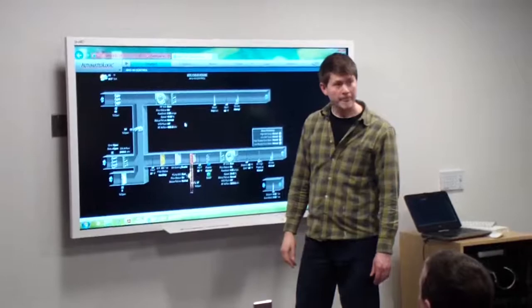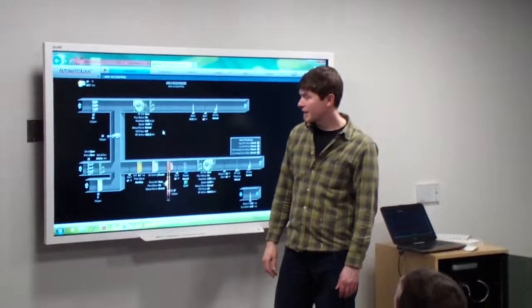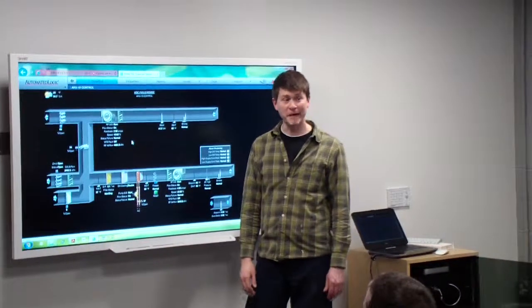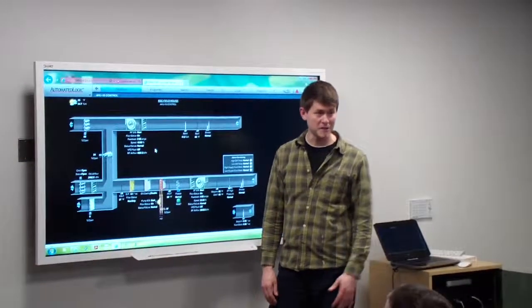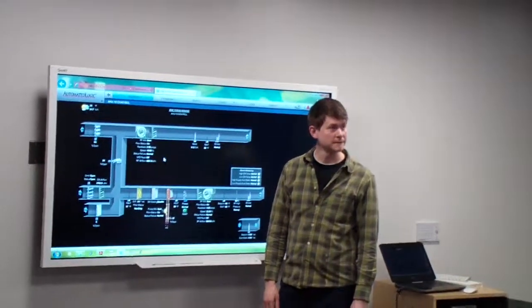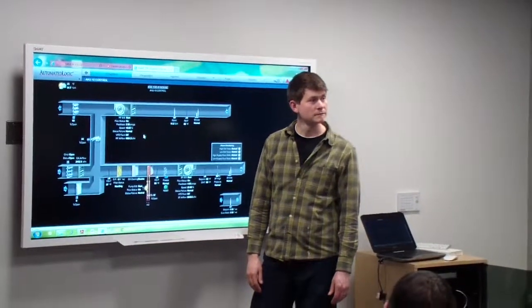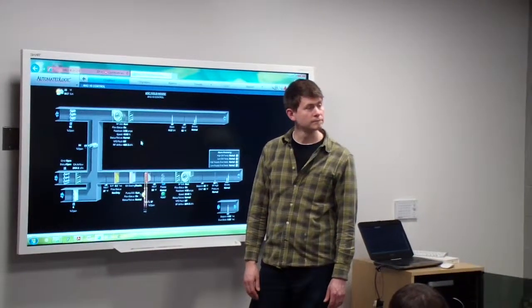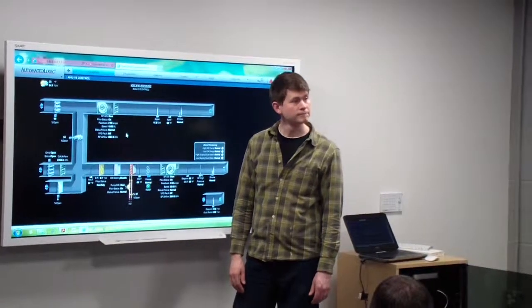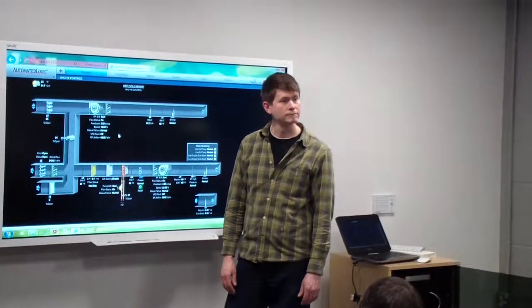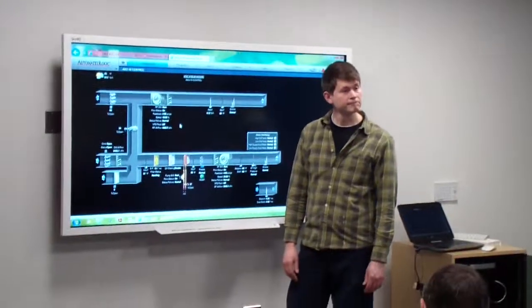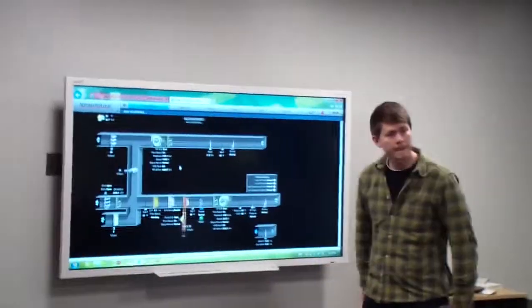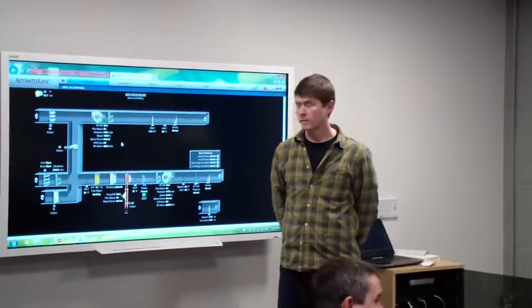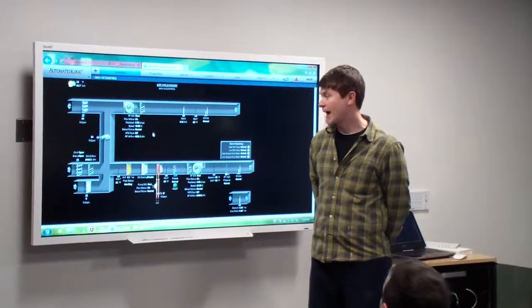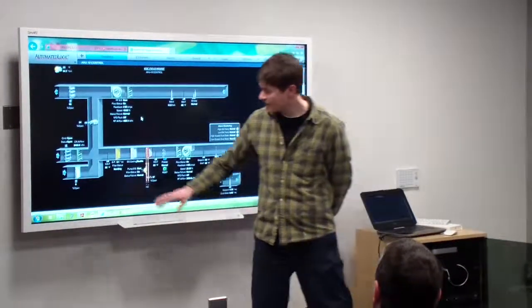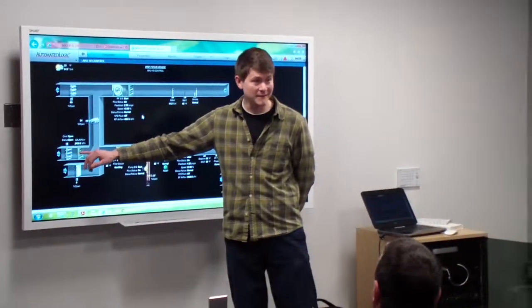Is that appropriate for a fitness space? I don't know the answer to that. That is what it called for in the spec, so that's appropriate to what the engineers believed. It should be based on usage, so we can question the engineer, but the design criteria would count that it is a fitness area, and so it should have the appropriate fresh air for that space. But is there ability to adjust that if we need to, or not? At this point, this is based off of what that damper size is.